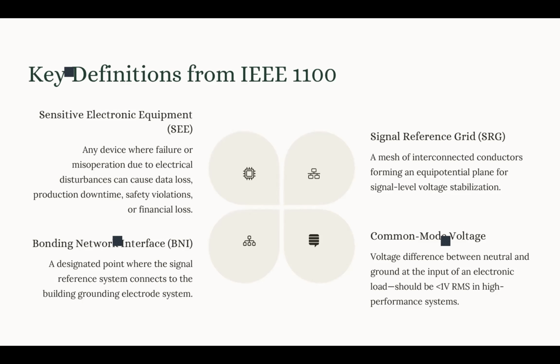And it is measured at the terminal of the electronic device. Okay, that's very important. Voltage difference between the neutral and ground, okay? And it's measured at the terminals of the equipment, okay? The input terminal of equipment. Now, you already know that theoretically we want the ground voltage to be zero. It's not going to be exactly zero in the real world, but we need it to be close to zero.